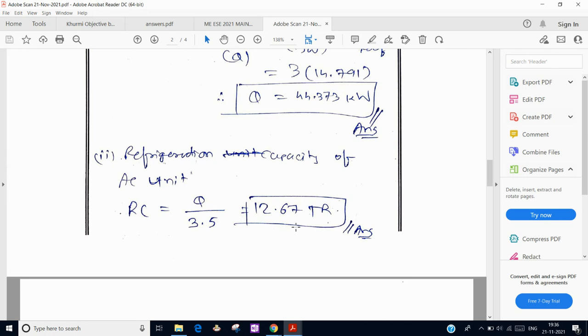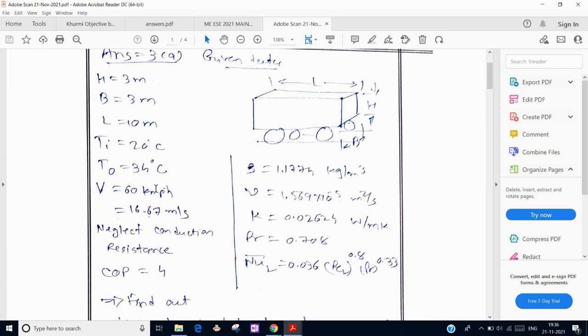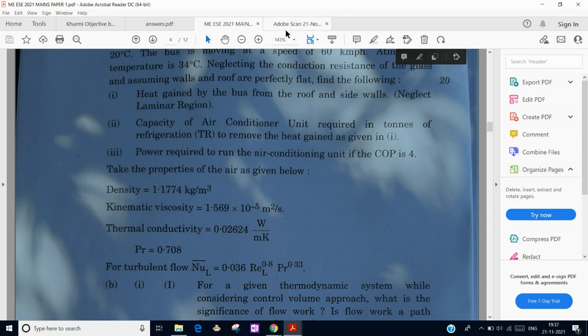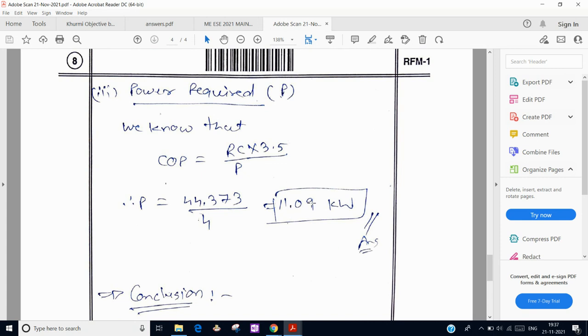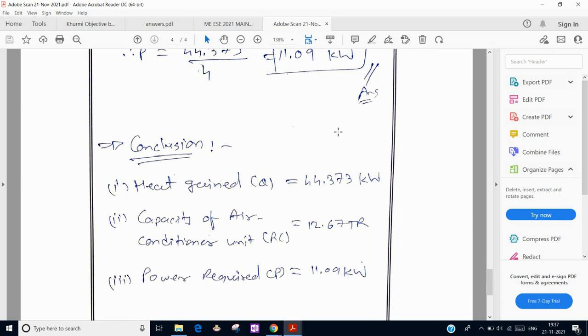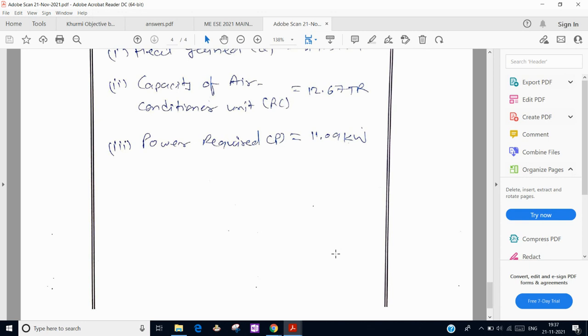For power required, we use Power = Refrigeration capacity ÷ COP. The COP value given in the question is 4. Substituting all values, the power required is 11.09 kW. In conclusion: heat gain = 44.373 kW, AC capacity = 12.67 tons of refrigeration, and power required = 11.09 kW.